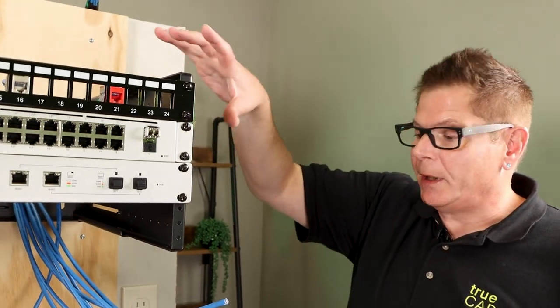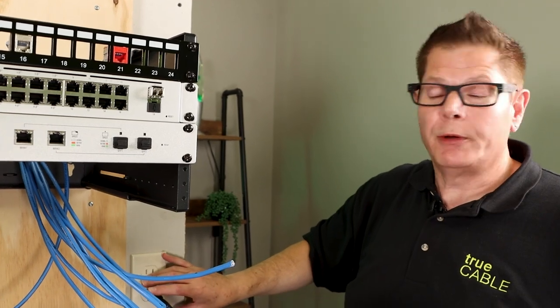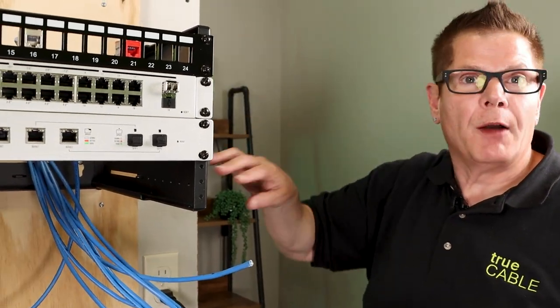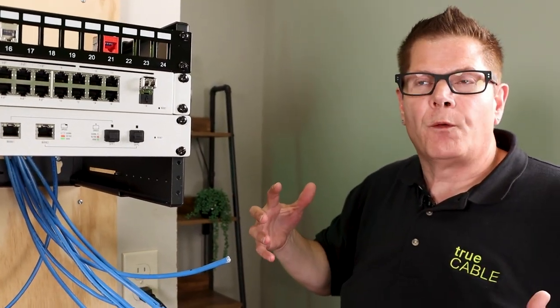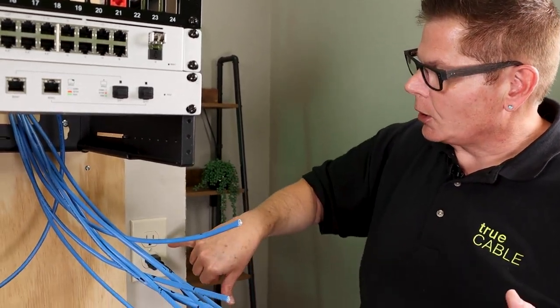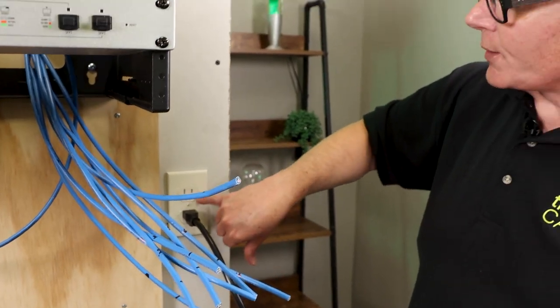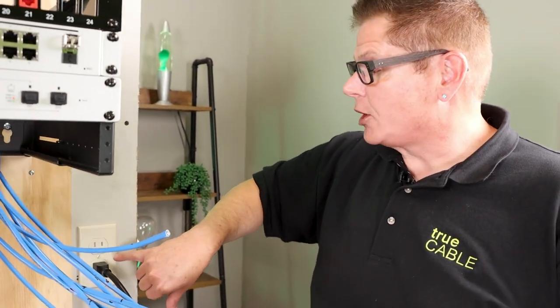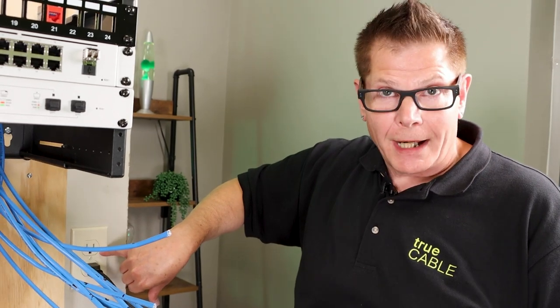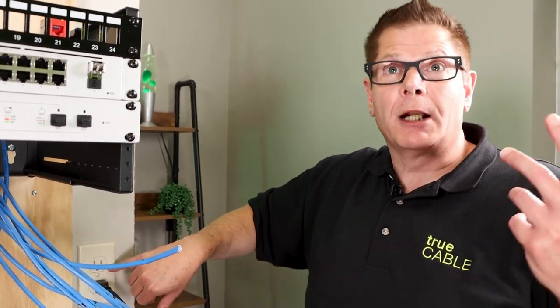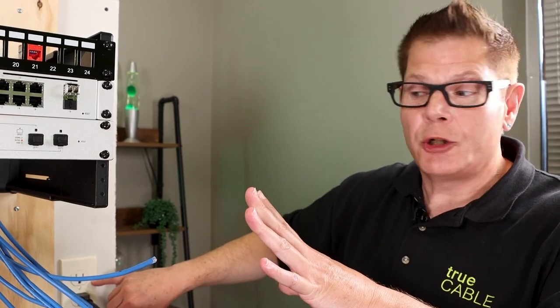and the equipment requires three-pronged grounding, you need a way to drain off any sort of electrostatic discharge from cable shields if you're running shielded cable. So that's going to occur at the outlet in this particular setup. So get yourself a three-pronged outlet tester and make sure that it lights up as correct. If it's not correct, get it corrected before you attempt an installation of this nature.